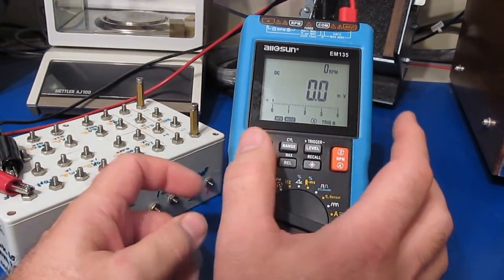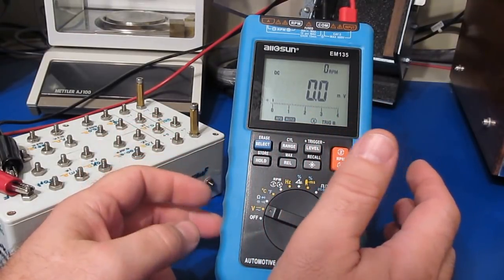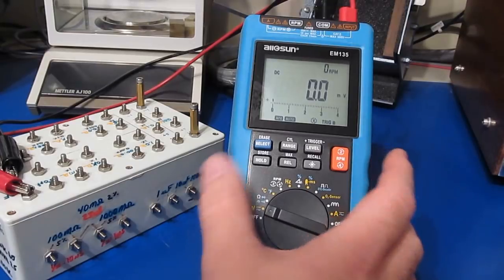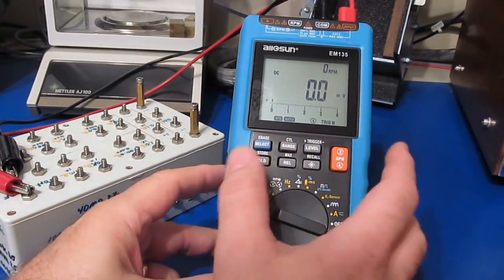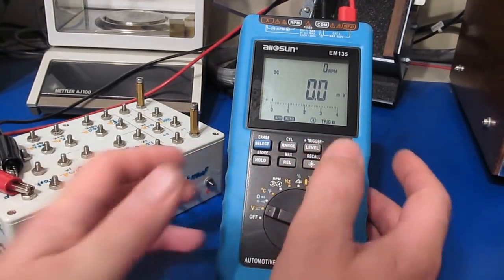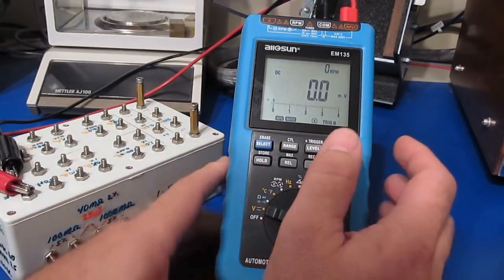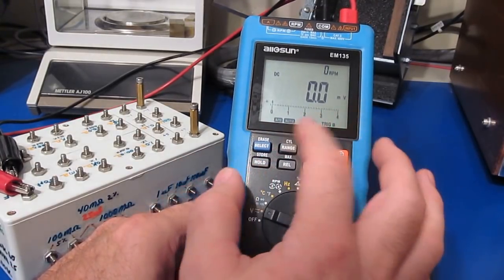The two PTCs in series are presumably for redundancy if one breaks down. The high impedance leg was left unchanged. A resistor was added for the tach input and drive side, and two MOVs were placed inside.